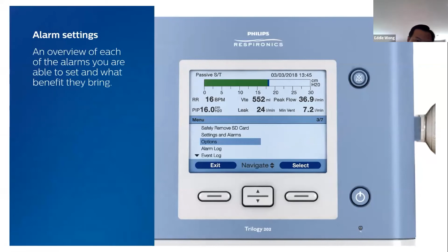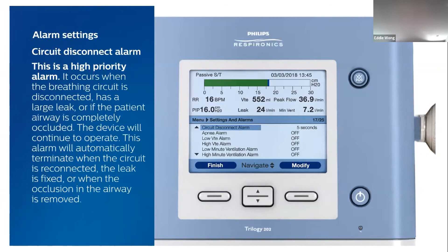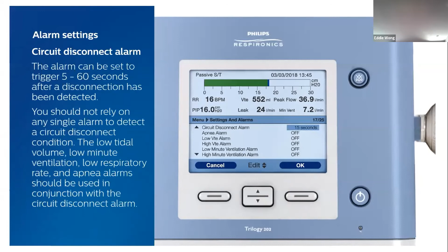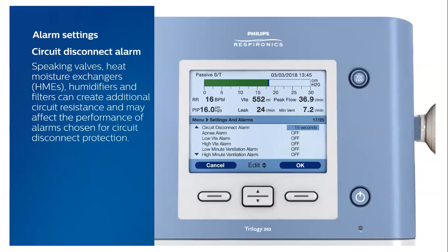The device will continue to operate. This alarm will automatically terminate when the circuit is reconnected, the leak is fixed, or when the occlusion in the airway is removed. You can set this alarm to trigger between 5 and 60 seconds from the moment the trilogy detects the disconnection. You should not rely on any single alarm to detect a circuit disconnect condition. The low tidal volume, the low minute ventilation, low respiratory rate, and apnea alarms should be used in conjunction with the circuit disconnect alarm. Speaking valves, heat moisture exchangers, humidifiers, and filters can create additional circuit resistance and may affect the performance of alarms chosen for circuit disconnect protection.